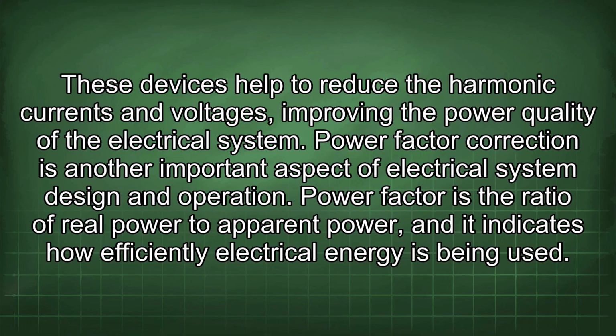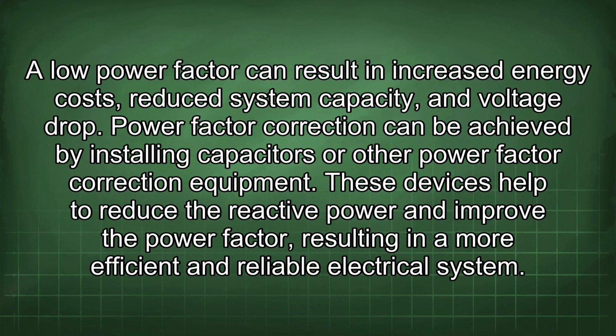Power factor correction is another important aspect of electrical system design and operation. Power factor is the ratio of real power to apparent power, and it indicates how efficiently electrical energy is being used. A low power factor can result in increased energy costs, reduced system capacity, and voltage drop. Power factor correction can be achieved by installing capacitors or other power factor correction equipment. These devices help to reduce the reactive power and improve the power factor, resulting in a more efficient and reliable electrical system.